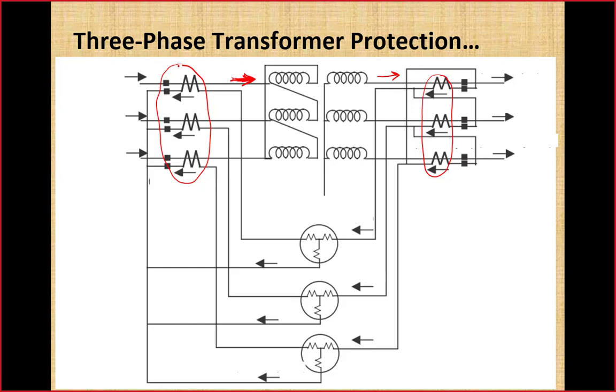Connection can be done either by connecting the dotted end with the dotted end or non-dotted end with the non-dotted end. In this particular example, where CTs are connected in Y configuration, we have made a star point on the dotted end of the CT secondaries. Due to this reason, now we are going to make the connection of non-dotted ends of the CT secondary on the other end with this winding. So it means now we will have to connect these CT secondaries in leading configuration with respect to non-dotted end.